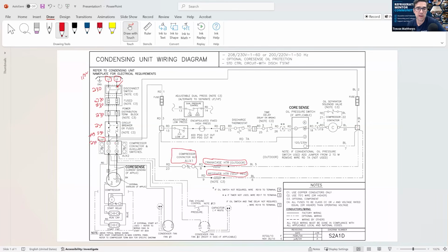Well, how does it even start up? Well, really, we don't have the evaporator on here, but as we see the L1, L2 coming off the upstream side, we go to our compressor safety circuit. So we got power going up and sending it up this way as we go across and we go up and we go over, and then we got our first fuse. Fuse 1, and it says red RD1. I'm assuming that's red line or red wiring. So we got power going there.